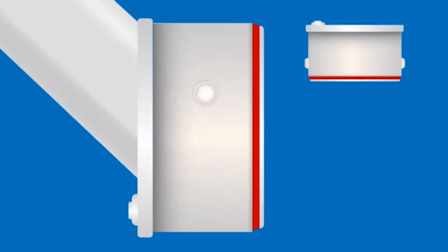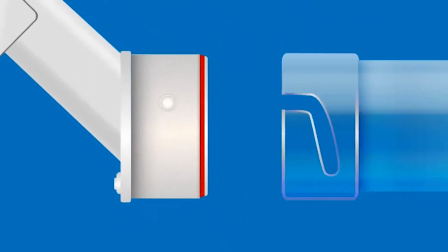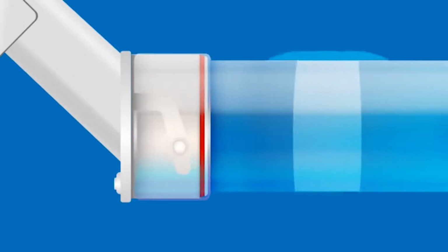Before continuing, make sure you use the lubricating jelly to lubricate the end of the transfer sleeve. Also, lightly lubricate the penis to prevent it from sticking to the inside of the penile tube during insertion, or while using the pump. The pump head has 2 small pegs on each side above the orange ring. These should be positioned into the 2 grooves on top of the penile tube. The 2 parts are then locked together with a twist, so that the 2 pegs slot down and locate at the lower end of the groove. If these 2 parts are locked together correctly, it will ensure the unit is sealed tight enough to create a vacuum inside the penile tube.